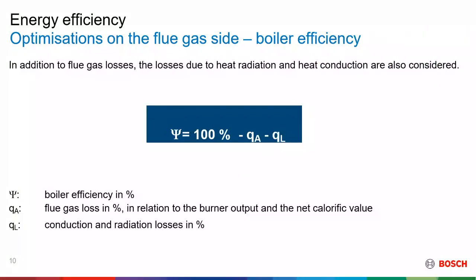Okay. So when it comes to measuring efficiency of a boiler, there are two ways in which you can measure efficiency. The first one being the direct method. The direct method is where you look at the calorific value of the fuel that you're burning, and compare it to the amount of steam you're producing. Okay? For Bosch, we use the indirect method. Here, which is on the screen, you look at the boiler efficiency from 100%, then you take out losses in the flue gas, and then you take out conduction and radiation losses. Then from there you can get your final boiler efficiency.